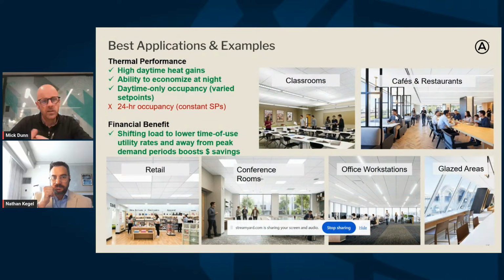When we think about what kind of buildings are good matches, we're often thinking about buildings that are predictably occupied - most often occupied during the daytime, empty at night. They could have variable occupancy throughout the day, but the key is the opportunity to shut the building down, not entirely, but do setbacks and leverage things like purging cooling early in the morning without creating occupant discomfort.